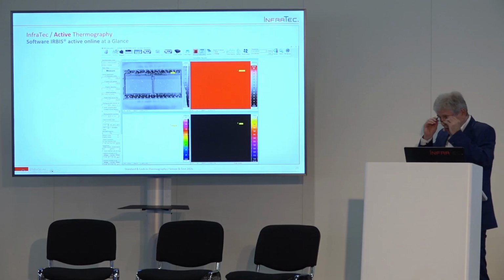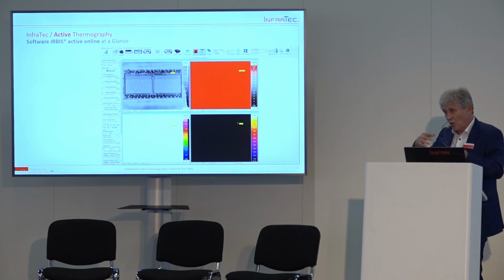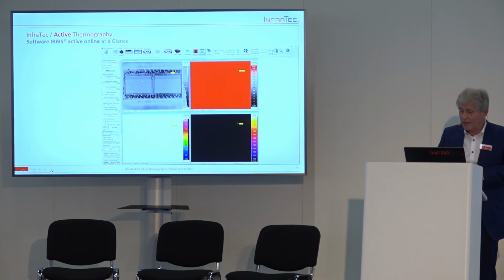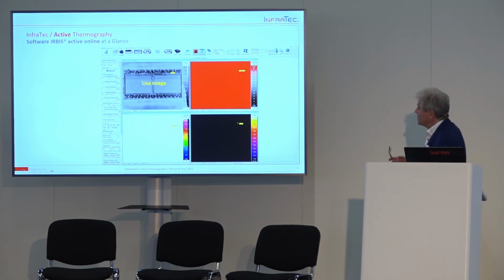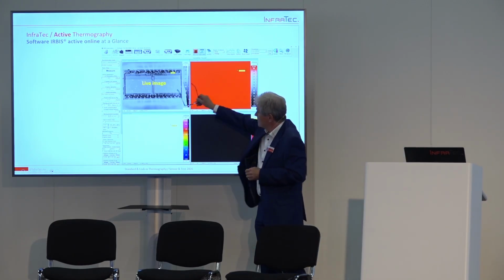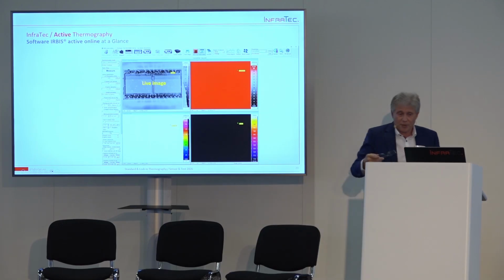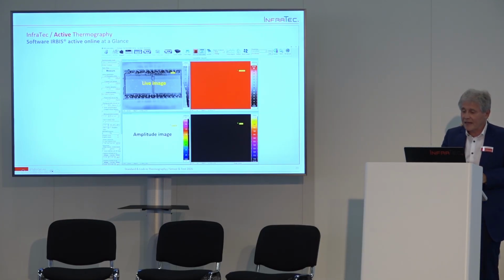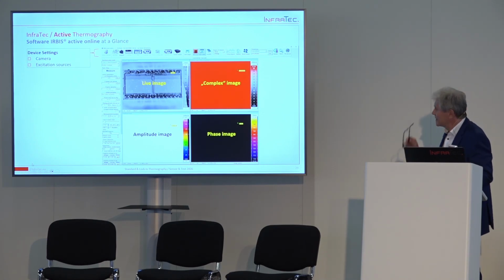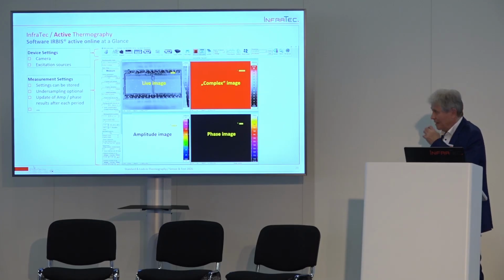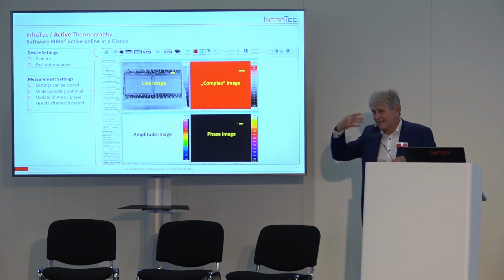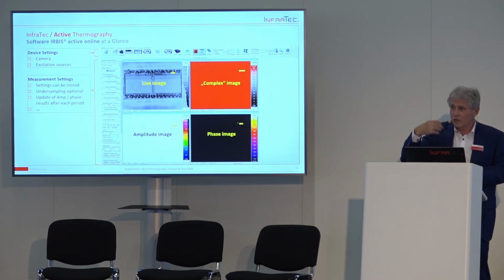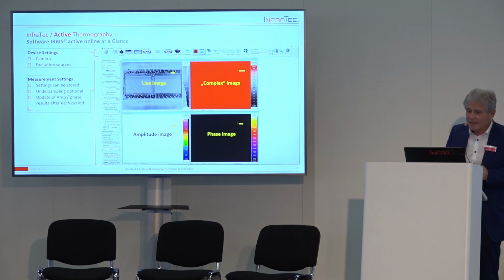Okay, so how to do that? You need a software. We can offer this kind of software. This is called Active Online. So with this software, you will get 4 images. On the upper left side, you see the live image during the process and during the excitation and the control of the camera. You get an amplitude image as a result, a phase image, and the complex image. This is our software for doing this analysis. You have some device settings. You need to set the camera, you need to control the camera, you need to adjust the correct temperature range and the frame rate, and then how many images we would like to process and so on.